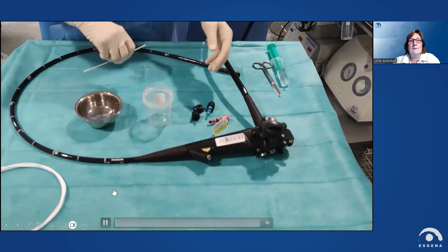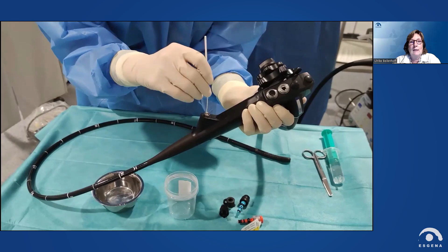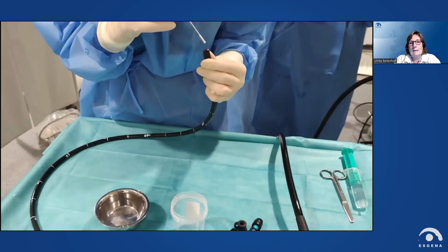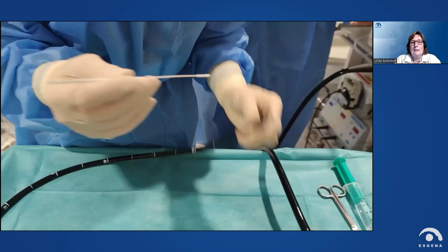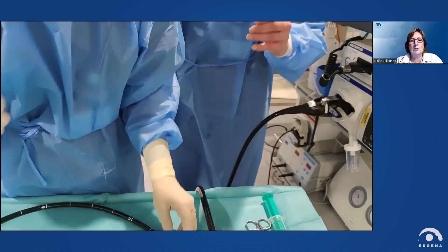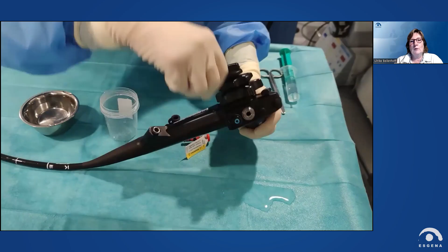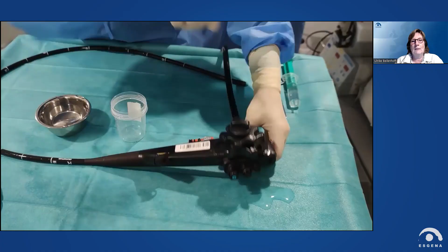You first do the swabs from the critical points, and you see the nurse doing that has sterile gloves and a sterile coat. We have a sterile covering of the table so that we really avoid any secondary contamination. And you also take a swab from the distal tip. If you have a duodenoscope, you really have to make sure that you go behind the elevator. Then you fix the valves you usually use for the endoscope, but you also need the cleaning valve in order to make sure that you can also rinse the air channel.